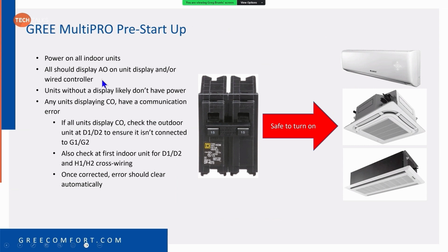Remember, some of these units, if you got a ducted unit, you don't have a display to look at. So you're dependent on looking at the wired controller for any error codes, whether it be an error code or an informational status code. AO is a status code. Any units displaying CO have a communication error. You need to figure out why you got a communication error.